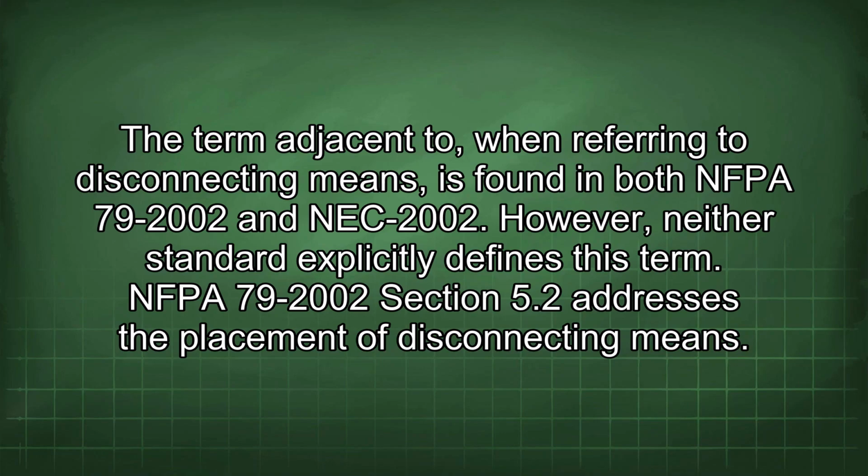The term "adjacent to," when referring to disconnecting means, is found in both NFPA 79-2002 and NEC-2002. However, neither standard explicitly defines this term. NFPA 79-2002 Section 5.2 addresses the placement of disconnecting means.